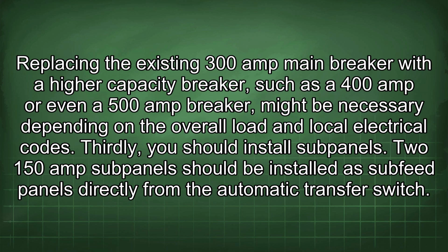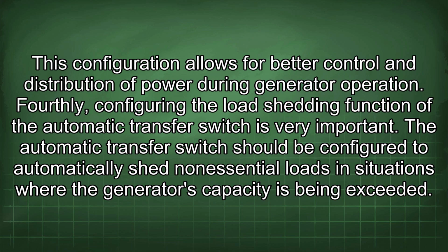Replacing the existing 300 amp main breaker with a higher capacity breaker, such as a 400 amp or even a 500 amp breaker, might be necessary depending on the overall load and local electrical codes. Thirdly, you should install subpanels. Two 150 amp subpanels should be installed as subfeed panels directly from the automatic transfer switch. This configuration allows for better control and distribution of power during generator operation.